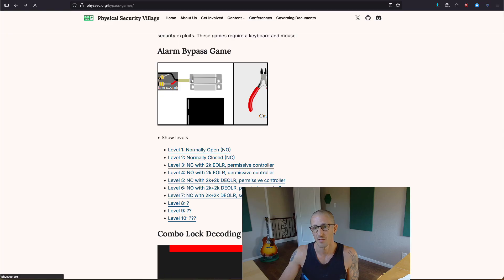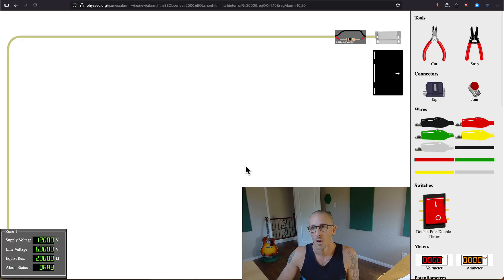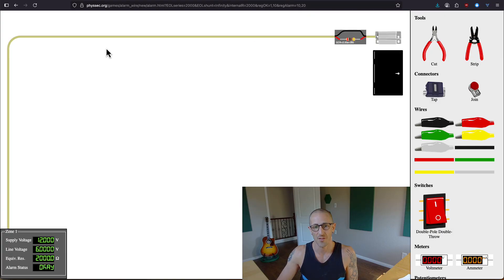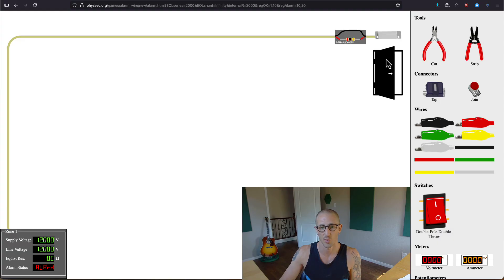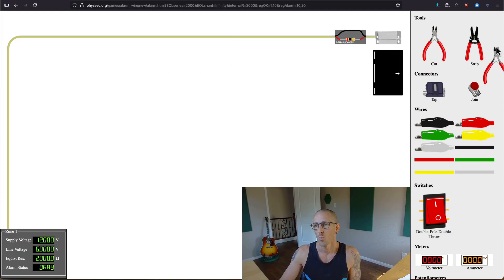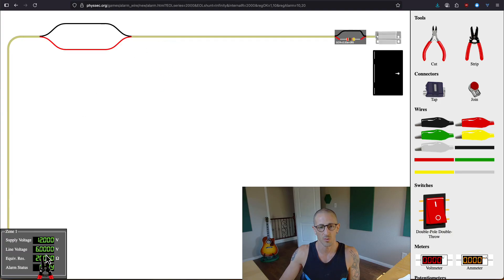We have permissive and sensitive modes — the sensitive ones will be more strict about the voltage values. With the end-of-line resistor, if we were to just short these wires together and produce zero volts, it's looking for six volts down here. It would basically say this is not right and throw an alarm, the same as if we open up the door. So we want to strip these wires, and normally we wouldn't have these values shown to us, so we need to measure them.